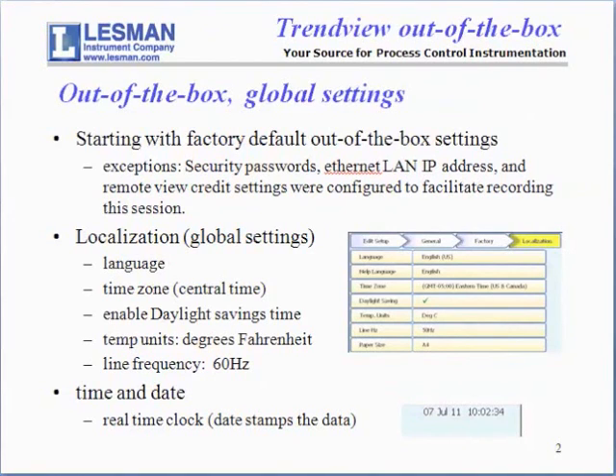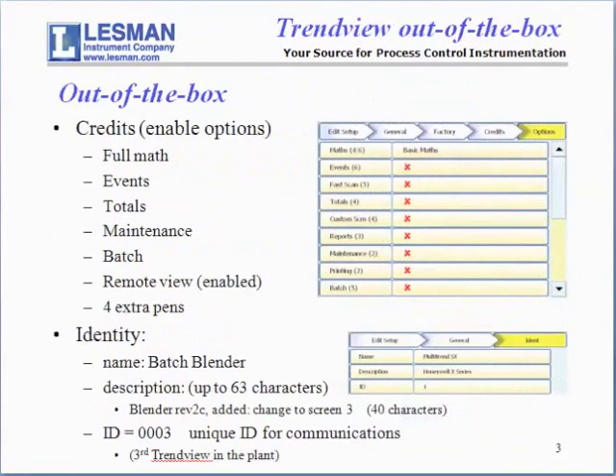These are global settings that involve the language. We're going to change the time zone from the default eastern time to central time, enable daylight savings time. The temperature units on a recorder are global and apply across the board. We're going to change it to degrees Fahrenheit, and we're going to set up for a line frequency of 60 hertz. The time and the date are important because all the data is time stamped, and then we're going to enable various credits. Credits are used to enable options.